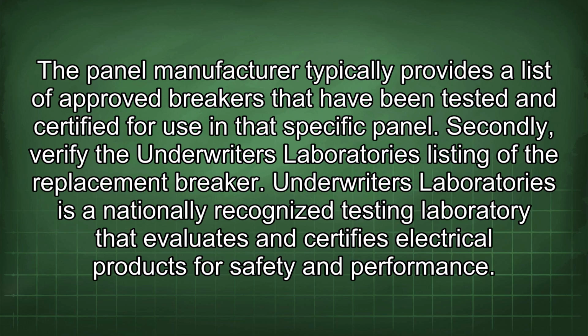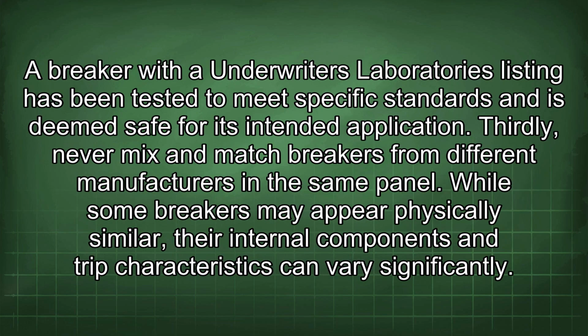Underwriters Laboratories is a nationally recognized testing laboratory that evaluates and certifies electrical products for safety and performance. A breaker with the Underwriters Laboratories listing has been tested to meet specific standards and is deemed safe for its intended application. Thirdly, never mix and match breakers from different manufacturers in the same panel.